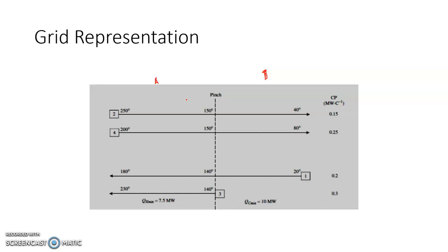Below pinch, hot streams move from pinch point 150 to their target temperatures of 40 and 80, while the cold stream moves from source temperature 20 to the pinch point at 140. The minimum hot utility is 7.5 megawatt and minimum cold utility is 10 megawatt for this particular problem.